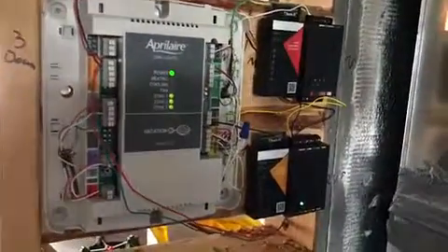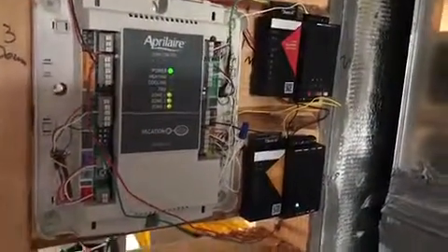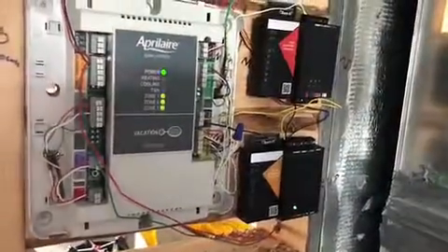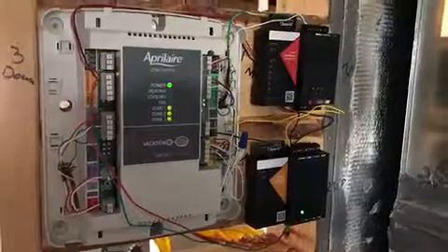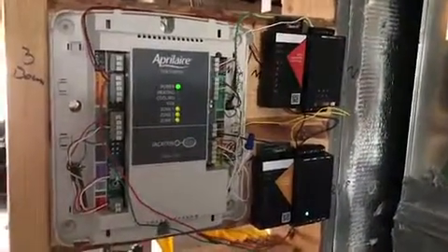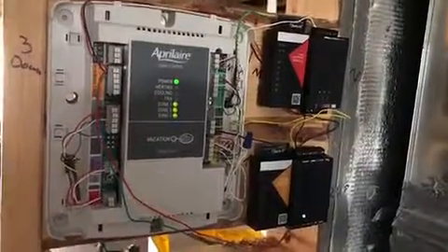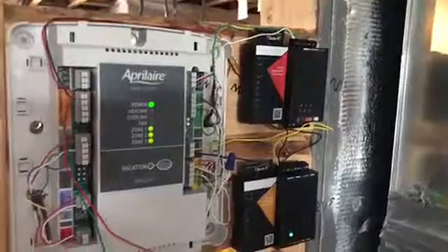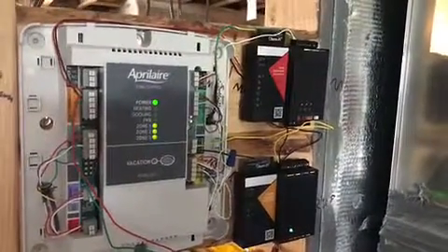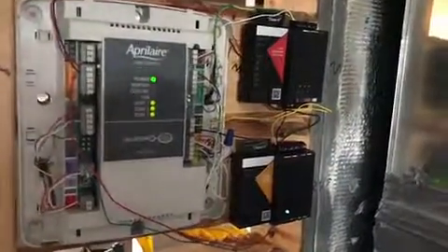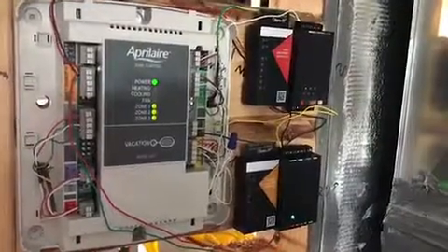Okay, here we've got the analog bridge installed as well. And what we're doing with this is controlling a damper for this particular zone controller. And so in order to convert this house, we brought the HVAC unit in right here. And so we can put in a thermostat upstairs. And then the analog bridge is brought in to control the variable damper.